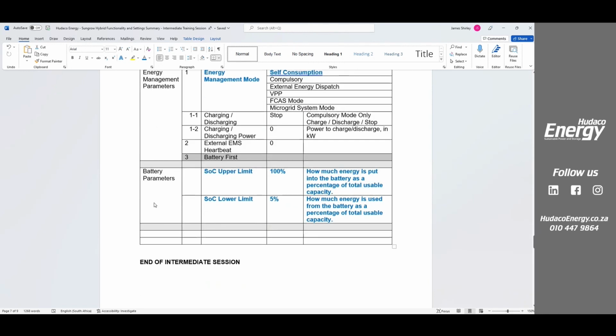And then finally, your battery parameters. So this is different to your state of charge. If you remember, I said that we've got two different options. The one is your upper limit, and the other one is your lower limit. So effectively, this is how much energy you can pull from your batteries. You can change this to 0% if you want to. And that would give you the 9.6 kilowatt hours or 16 kilowatt hours or 19.2, whatever, usable, which is a different value to that reserve state of charge.